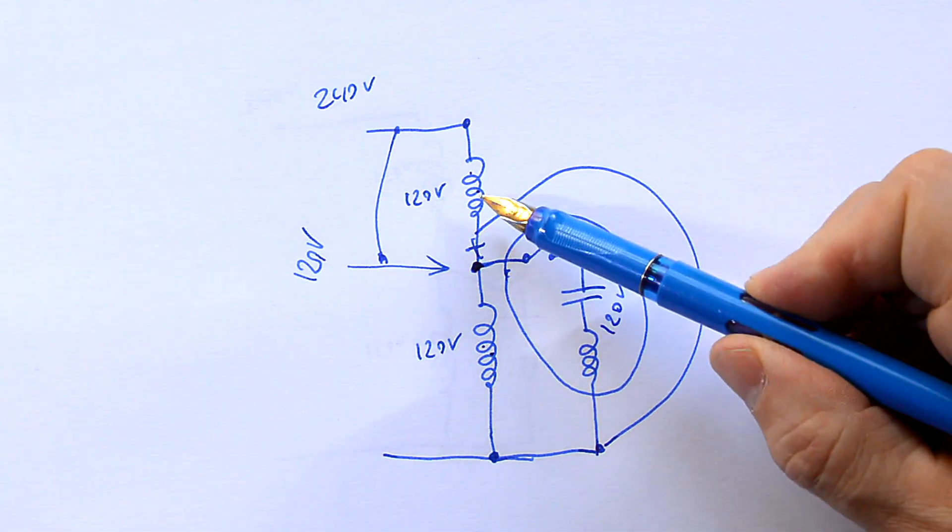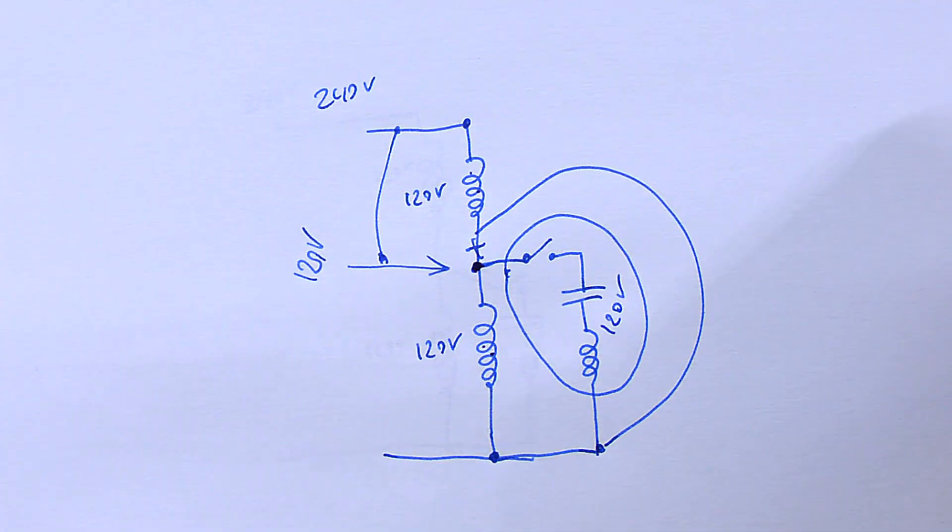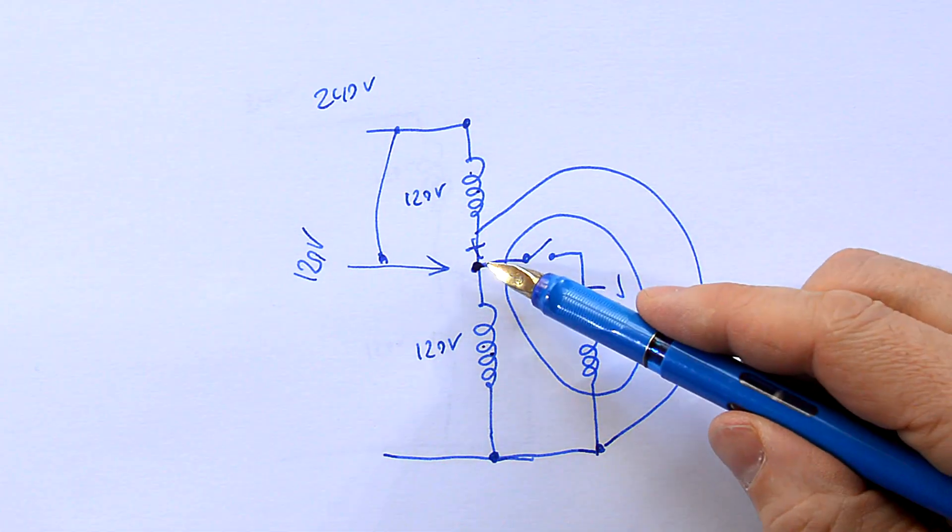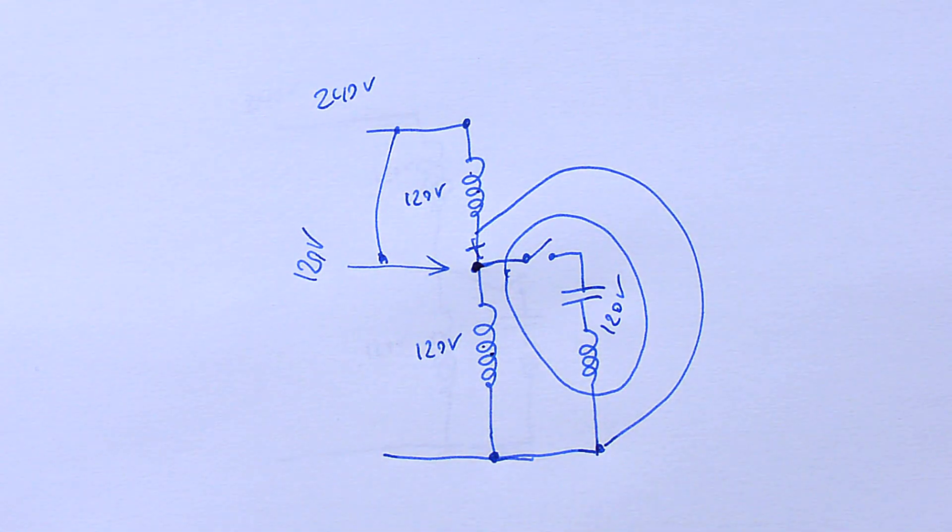And you might say but isn't that gonna throw these two coils out of balance? Not really because inside the motors these two coils are actually right on top of each other. So the motor acts very much like a transformer.